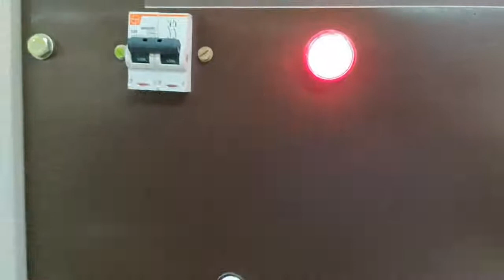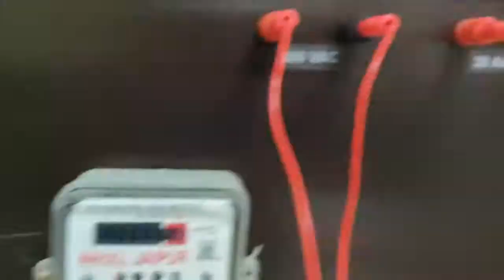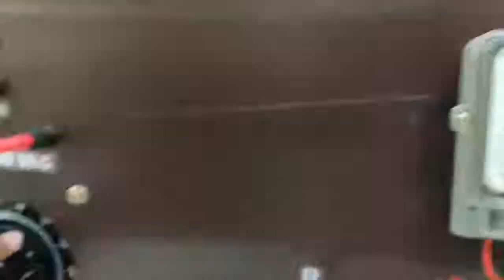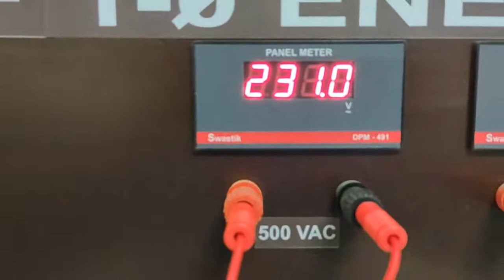Let us vary the variac so that rated voltage will be applied. Here I am applying the variac. You can see the reading in the voltmeter as I increase the variac voltage, up to 230 volts. I am applying the voltage using the variac. You can see the voltage as 230 volts. I have applied rated voltage to the energy meter.